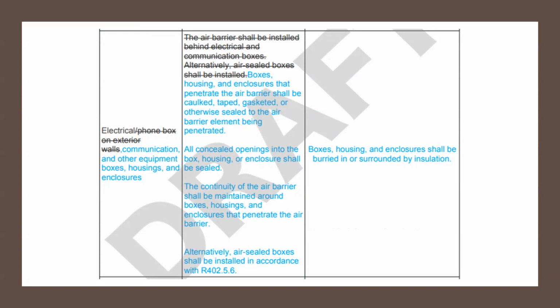blue is all new or reworded. It basically just says electrical, communication, and other equipment boxes and housing and enclosures. The air sealing requirement is boxes, housings, and enclosures that penetrate the air barrier shall be caulked, taped, gasketed, or otherwise sealed. All concealed openings to the box, housing, or enclosure shall be sealed. The continuity of air barriers shall be maintained around the boxes, housing, and enclosures that penetrate the air barrier. Then it says, alternatively, air sealed boxes shall be installed in accordance to, and it talks about that requirement.